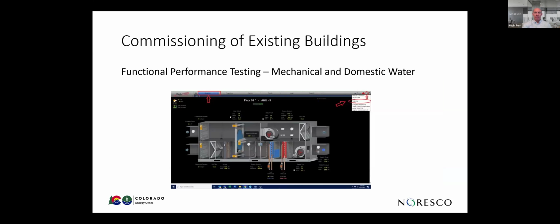All right, number 3, functional performance testing. So in this section, we talked about HVAC, domestic water heating, and controls. Later in the next couple slides, we'll talk about the lighting a little bit more in depth, or the electrical testing. If for some reason you can't test a mode of operation, say it's 90 degrees outside and you need to test heating mode, you can have seasonal testing or deferred testing. So you would come back later on and say, hey, on September the 30th, the weather is going to be cold enough for us to test heating on this particular piece of equipment. We will do testing of that sequence only then.